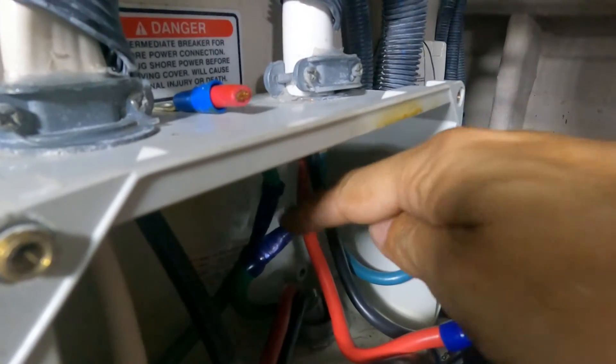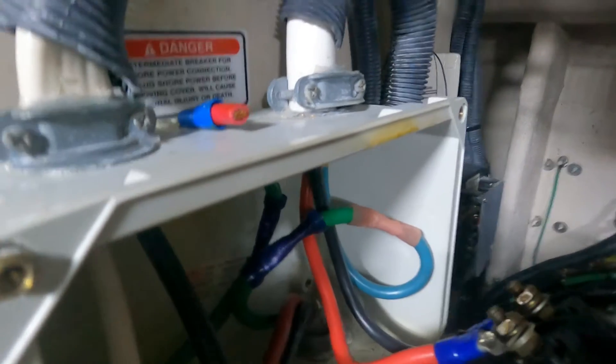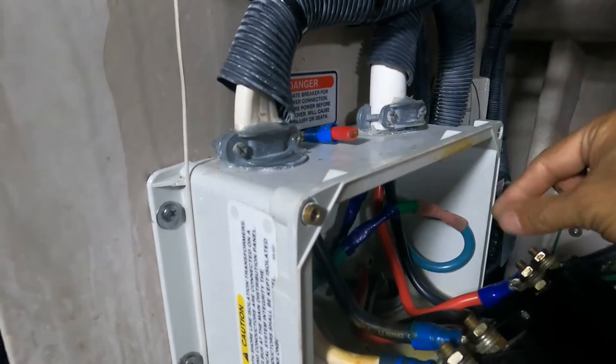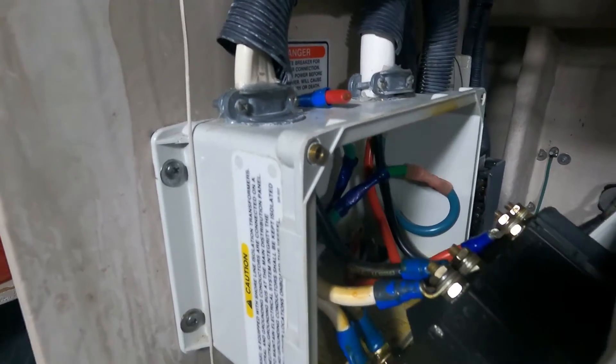You see this — this boat doesn't have a galvanic isolator. Originally they interrupted the cable to install the galvanic isolator over there, but they never installed it. We are going to cut it here and here, extend those cables, and make a hole here to install the galvanic isolator over there.